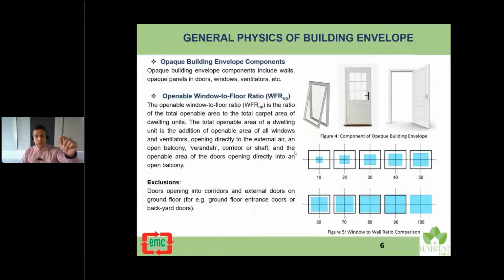When I say openable, the part that's openable is what you need to account for, not the fixed part. For example, a top hung window opening with a door below: the door can open 100%, the entire panel opens, but the top hung window might only open 25% or 35% - the manufacturer's catalog will tell you. You take the measurement of the window but consider only the openable percentage, say 30% or 40%, in your calculation.